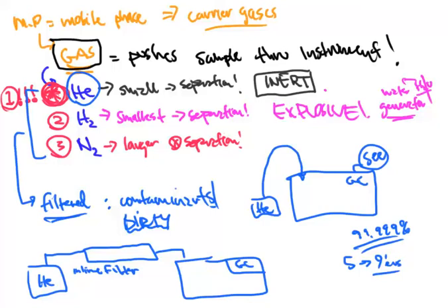However, in our laboratory, even though we order the 5 niners to run, we still have an inline filter that's in between the helium and the GC unit because we still don't want trash to get inside of our GC system. Because this thing's expensive. And we would rather take the extra steps of paying a little bit more for some cleaner gas and still including the use of a filter just to remove all the dirtiness that we can before it goes into this really expensive piece of instrumentation. All right? So that's the purpose of the inline filter. That's the gas that we typically use, helium.